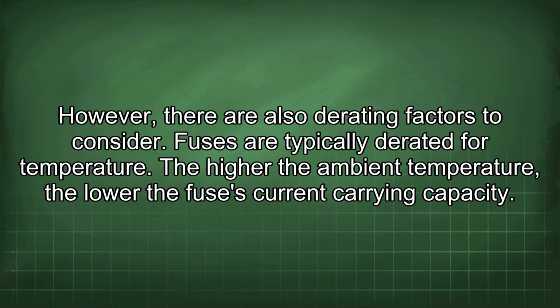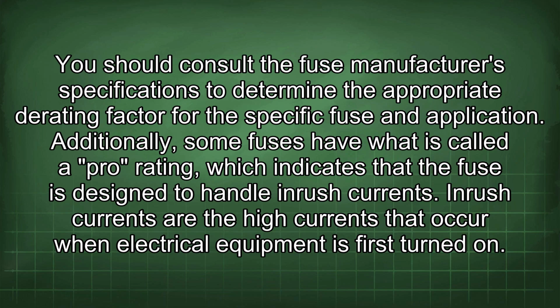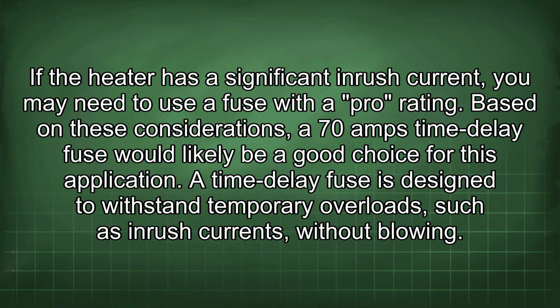However, there are also derating factors to consider. Fuses are typically derated for temperature. The higher the ambient temperature, the lower the fuse's current carrying capacity. You should consult the fuse manufacturer's specifications to determine the appropriate derating factor for the specific fuse and application. Additionally, some fuses have what is called a "pro" rating, which indicates that the fuse is designed to handle inrush currents. Inrush currents are the high currents that occur when electrical equipment is first turned on. If the heater has a significant inrush current, you may need to use a fuse with a "pro" rating.